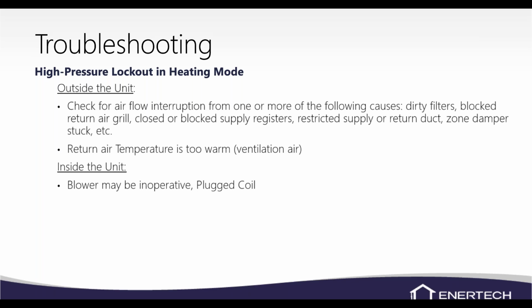Obviously, inside the unit, the blower is an obvious sign. If you ever see the blower rocking back and forth on an ECM, it's trying to find direction, so it's confused, and more than likely the module on the motor is the issue. It seems like that's normally the case anyway, that the module is what fails on the ECMs and not the actual motor itself. Not that I haven't seen motors fail, but it's normally the module.